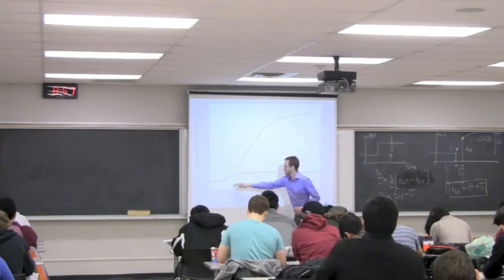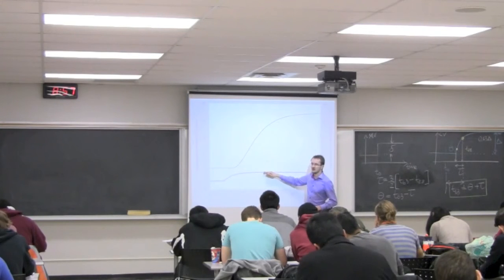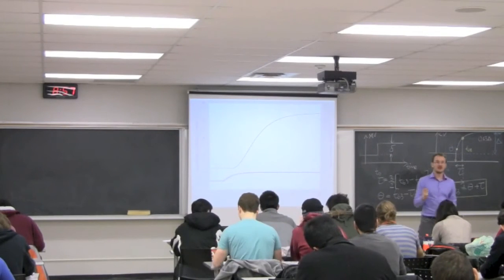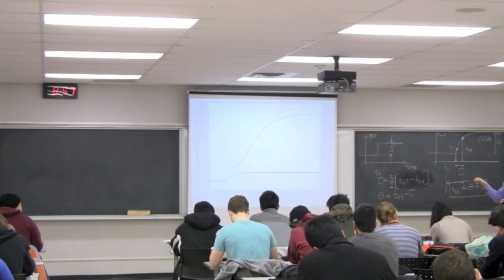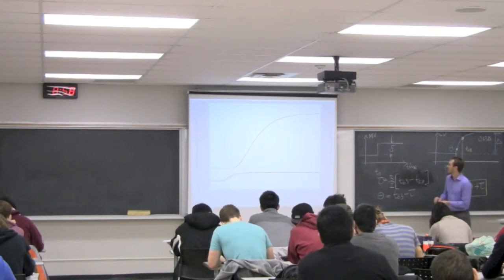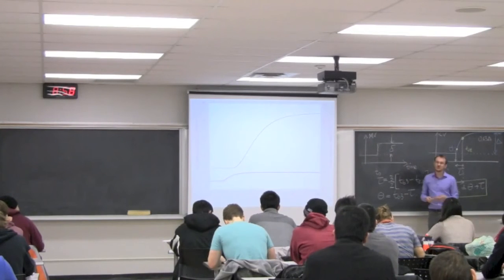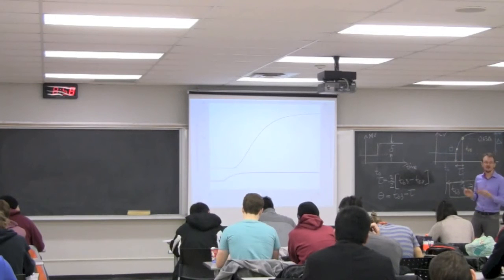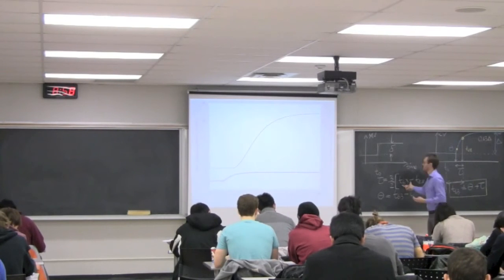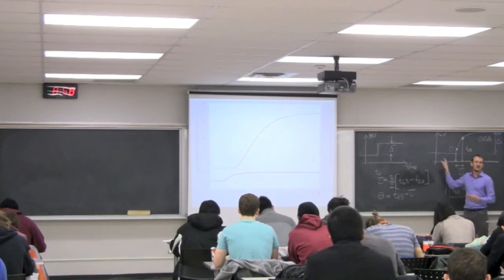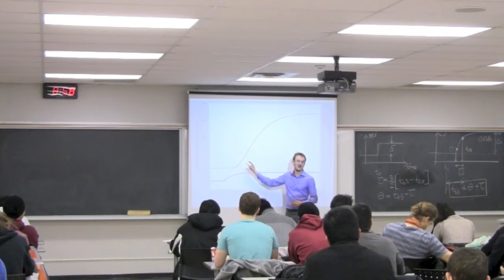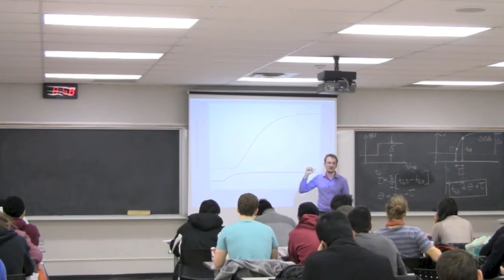Initially, many people thought you could use it. It looks nice, looks first order, right? It looks like it should be valid for what our approach is, but here's one reason why we cannot. This input in blue was not done appropriately. The input in blue is this manipulated variable. The manipulated variable must be stepped up. Here, we're putting in a smooth change in the manipulated variable that slowly opens the valve to the new value. The beginning is okay, the end is okay, but this middle part is not okay. You must, when you make this change, open that valve as rapidly as you possibly can. Not slowly open, open, open, open. This change should be as step-like as you can possibly make it. Now, obviously, in reality, we won't quite get a perfect step. There will be a little bit of a curvature over there, but you should make it as step-like as possible.